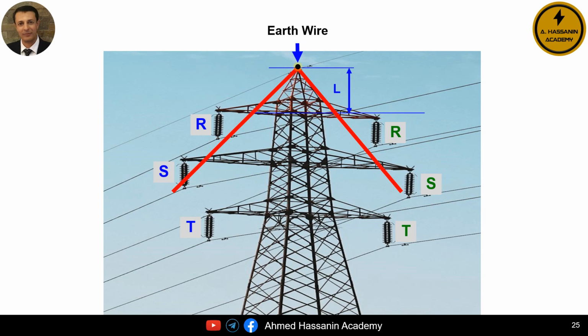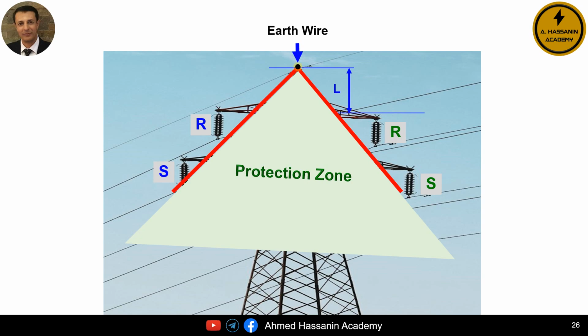However, we will notice that the protection zone has changed because the width of the tower has increased, or in other words, the horizontal distances and spacing between the phase conductors have increased. Therefore, we can understand from this that unfortunately, the protection zone does not cover or protect all the insulators or conductors of the tower. As we can see, the insulators of the phase conductors R and S, whether for the first circuit or the second circuit, are located outside the protection zone. This, of course, means that if a lightning strike hits this tower, it could very easily damage the insulators of phases R and S for both circuits.